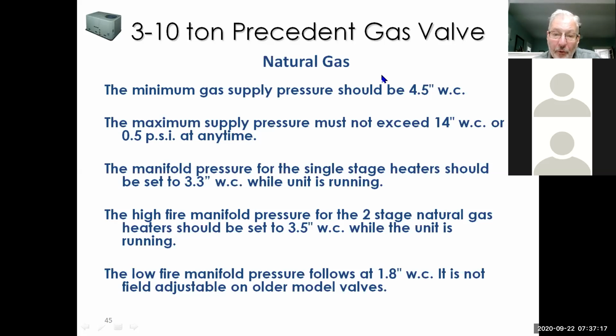Manifold pressure on a single stage should be 3.3 inches. And on the two-stage models, we should look at 3.5 on high fire and 1.8 on low fire. And this is for natural gas. So those are the pressures we're looking for when we're working with the Precedent models or the YSC models.